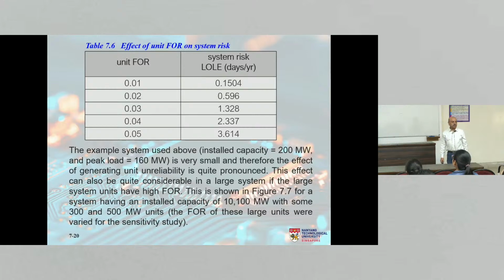Now we change the forced outage rate of the generators. We change the unavailability of the generators, because that's also not known to us. In the years to come, the manufacturer is telling us, based on past data, that the forced outage rate of this generator will be 1%. But we know that it is uncertain. So we can also include that uncertainty and change the forced outage rate. When it was 1%, our risk was 0.15. If it goes up to 5%, the risk will be 3.6 days per year. So we can quantify everything.